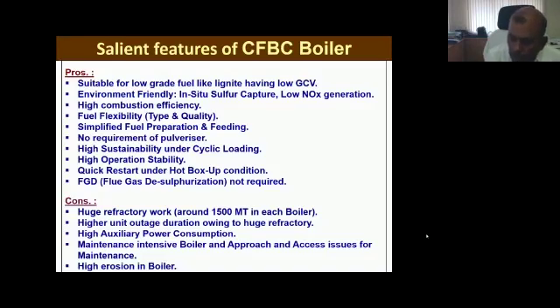And then on the combustion side, when we fire this lignite in the combustor, it goes to the cyclone, and unburned particles along with the bed material, which is a heating element in the combustor, come back again to the combustor. So it recirculates inside the combustor and cyclone until there is complete combustion, almost 98 to 99%, more than 98%. The residence time is infinite, whereas in a conventional thermal power plant it is not, so this supports the environmental requirements. High combustion efficiency and fuel flexibility, as I already discussed, with lignite. I would like to highlight here that for a certain percentage we have used imported coal also, with 10%, 15% and 7% variations, considering the low grade of fuel. Though it was designed for lignite, we are firing imported coal also.